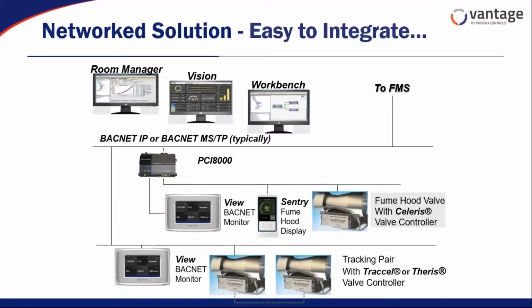or Theris valves. Now, the Traccel and Theris product line, which is for our non-fume hood research environments or for our healthcare environments, you can get those either in a direct LON connection or a direct BACnet connection, which can go typically on the BACnet MSTP network inside of a building that goes to the building automation system. So for those devices, you have a choice to have native MSTP or native LON that can go directly on the building backbone. And in that particular case, we don't need any type of an integration device.